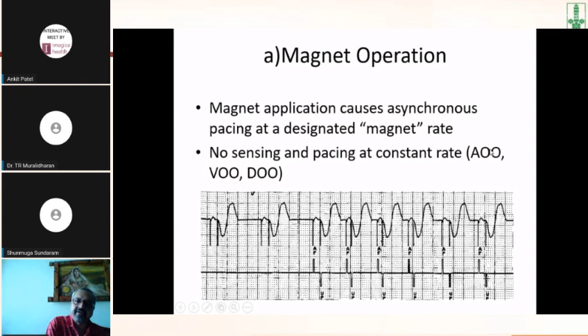The magnet rate is typical for each company. It's different. For some companies it is 90 beats per minute, for others it is 100 beats per minute. So it's very important to know the magnet rate value of each company, and more importantly, this is useful at follow-up, because if, for example, the magnet rate of a particular make or model is 100 beats per minute, and if it drops down by 10 to 15% at follow-up, it's an indication of battery depletion. So if from 100 it falls down to 85 beats per minute, it may be cause for interrogation of the device to see about elective replacement of the pulse generator.